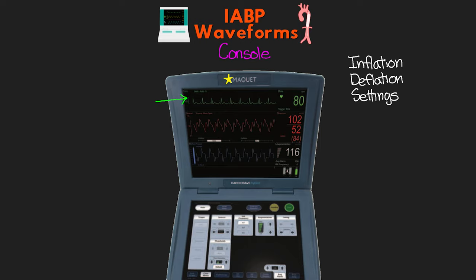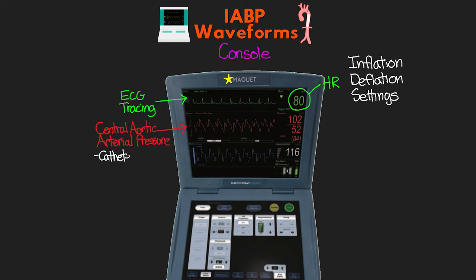I want to point out a few important parts in the top display screen. At the very top, in green, you're going to see your patient's ECG tracing. To the right of this tracing, you'll see your patient's heart rate — in the example here, it is currently 80. Below that, in red, is going to be your patient's central aortic arterial pressure waveform. This waveform is actually coming from the balloon pump catheter tip, using either the pressure lumen or a fiber optic sensor. To the right of this waveform, you will see the values for systolic, diastolic, and mean pressures.